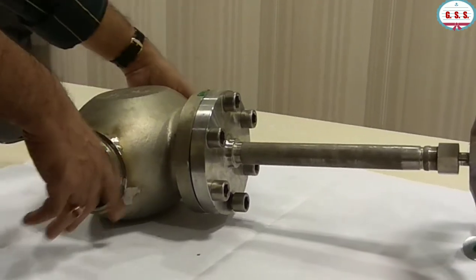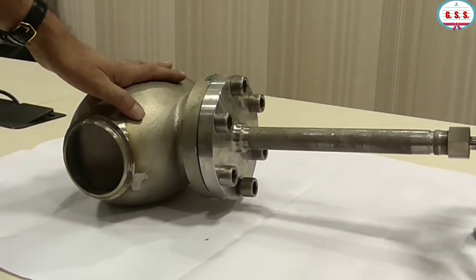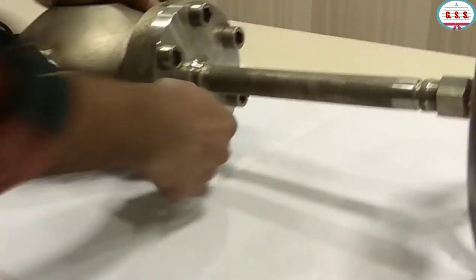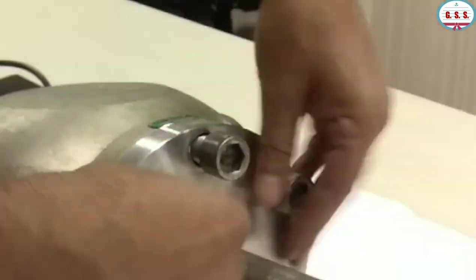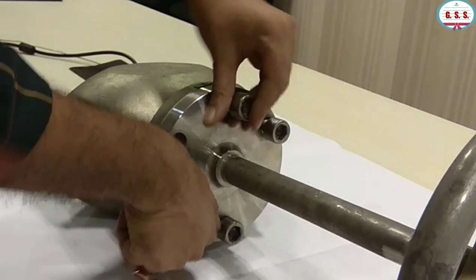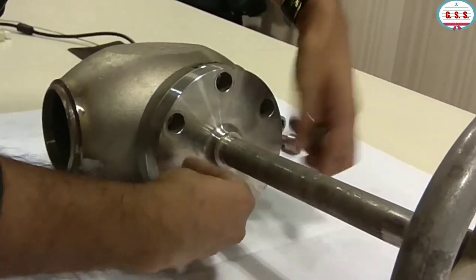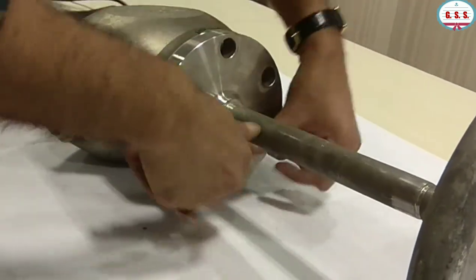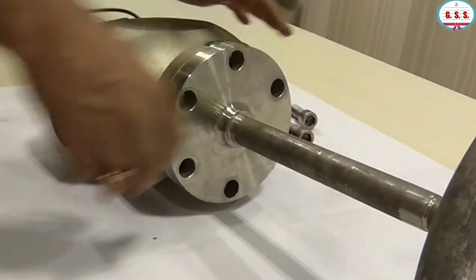If the valve is welded directly to the pipe in this assembled condition, the soft seat will melt or be distorted and there will not be 100% leak tightness. So what should be done at site? There are six body-bonnet bolts. These bolts have to be opened using an L-key. At site, before welding with the pipeline, this body-bonnet joint should be opened and the upper part has to be removed.